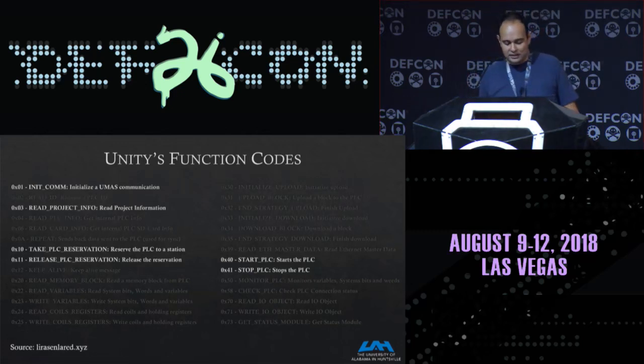So basically we'll start a communication - init communication. We'll read a project info to read some data about the project. This is also cool - take PLC reservation. It means the PLC needs to be connected to someone; someone needs to reserve the PLC. If you take the PLC reservation, you're taking the other party down. This is DOS built into the protocol, dudes.